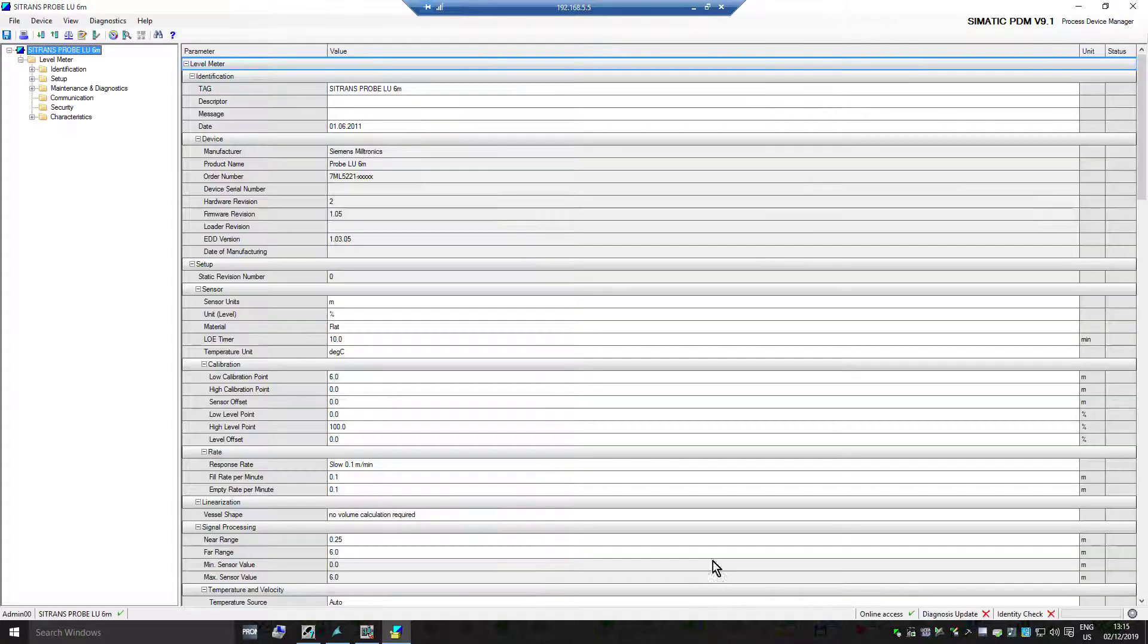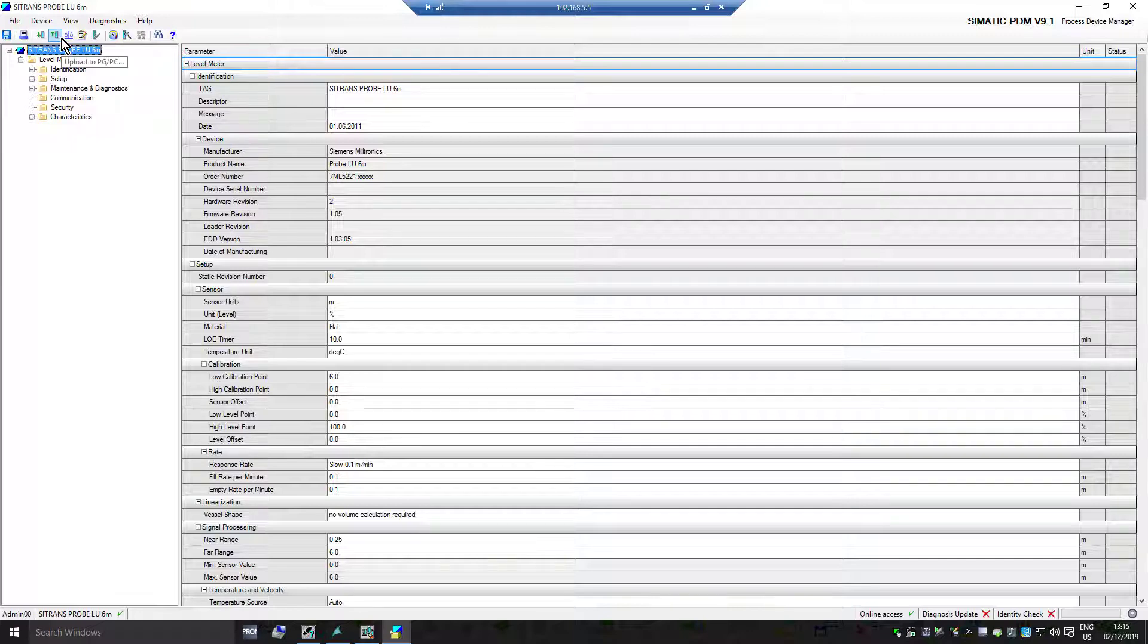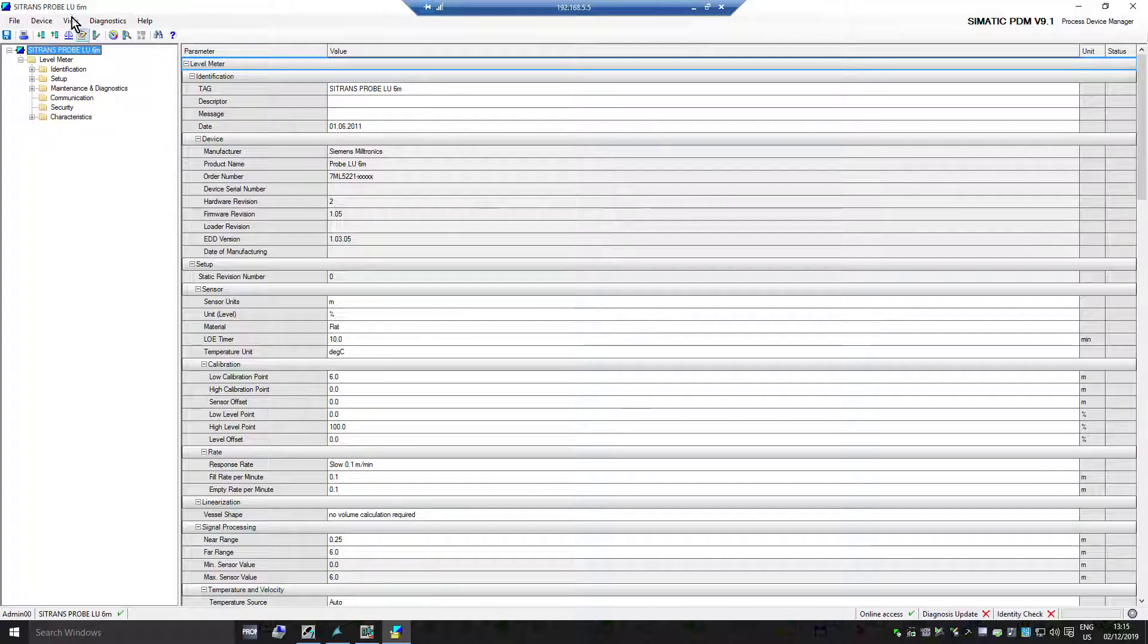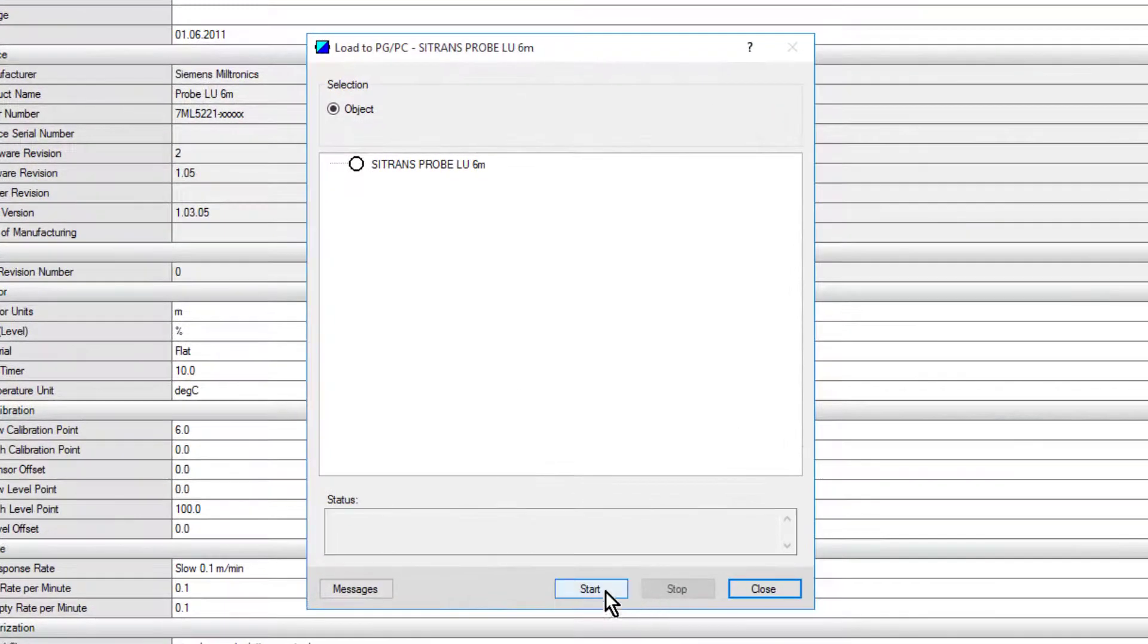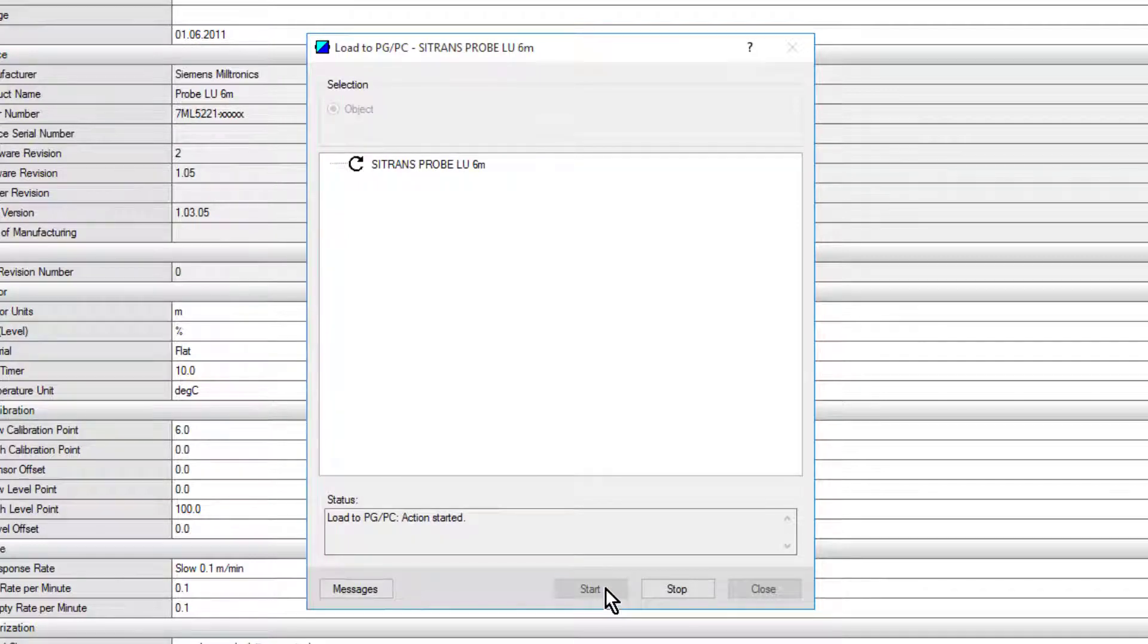Now the probe actually out in the field hasn't changed, but because I put this into the project, this is the default set of parameters. So the first thing we need to do is synchronize the project - we need to re-upload. You can see now it's done an upload because it's got the tag from the device. You'll see these symbols on the right hand side will change any parameters that it's struggled with.